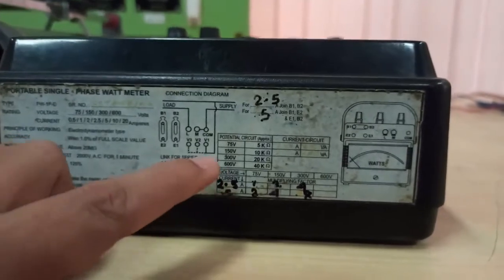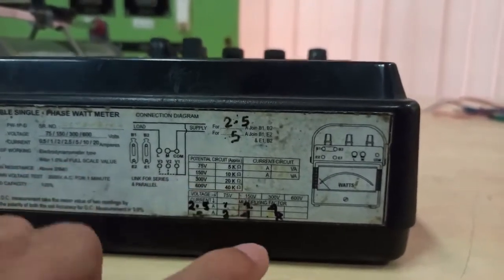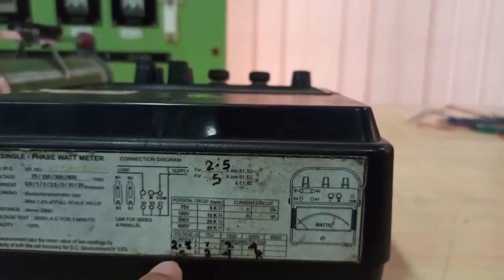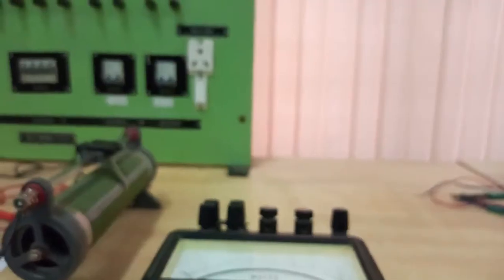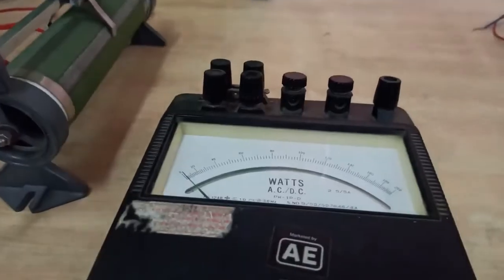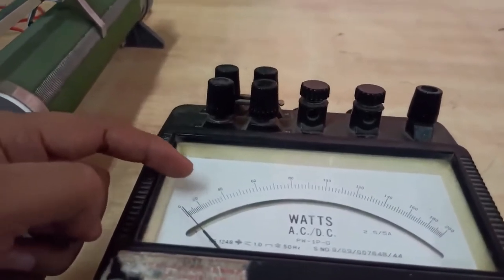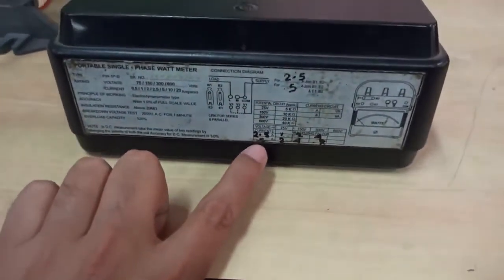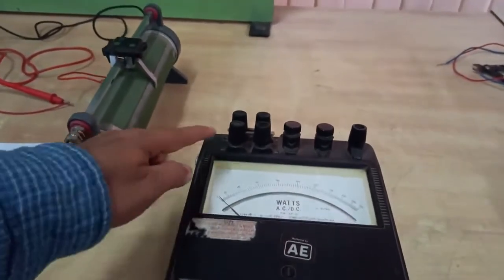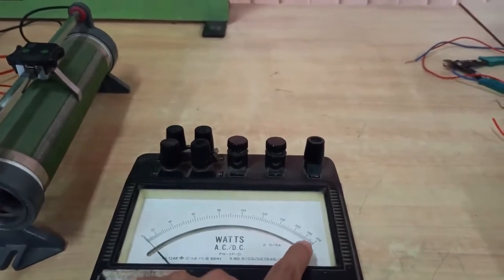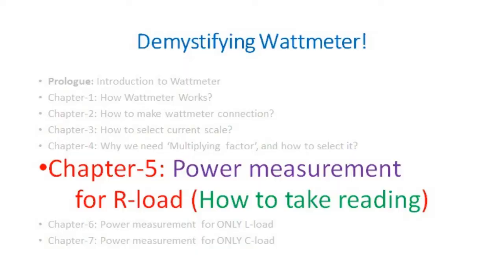On the wattmeter you will find a reference table listing current and voltage scales. For example, if you select 2.5 A and 75 V, the multiplying factor is 1; if you select 5 A and 150 V, the multiplying factor is 4. If the display table is not available, you can calculate it: multiply the current scale by the voltage scale, divide by the full scale deflection value, and take the nearest integer.